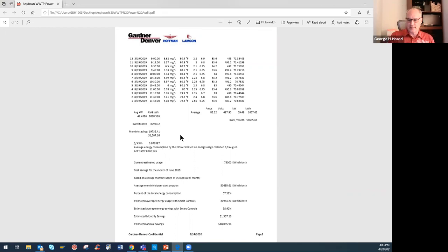So I guess to try to tie this up, I had mentioned before, I basically focused on multi-stage centrifugals here. Some of the newer technologies, like the PD screw blowers, positive displacement screw blowers, as well as the high-speed single impeller centrifugals, whether that be airfoil turbo, mag bearing turbo, or inner-geared centrifugal, are typically considered to be the more highly efficient offerings out there. So you could do an energy audit on one of those types of blowers, but you probably would get less benefit from the results.